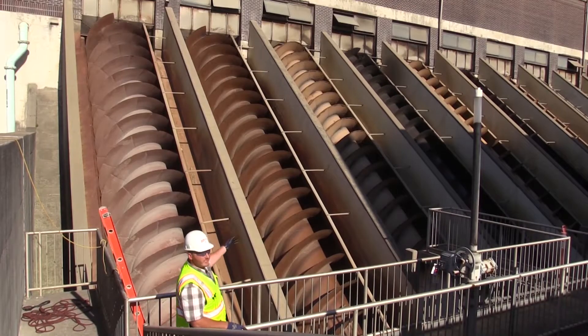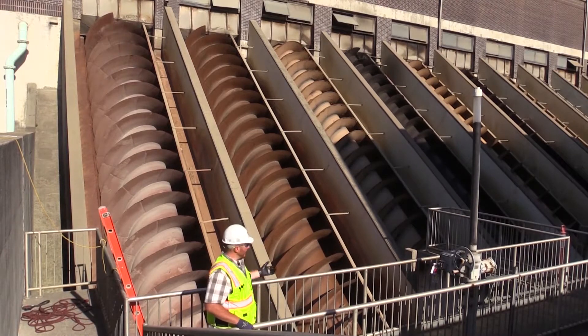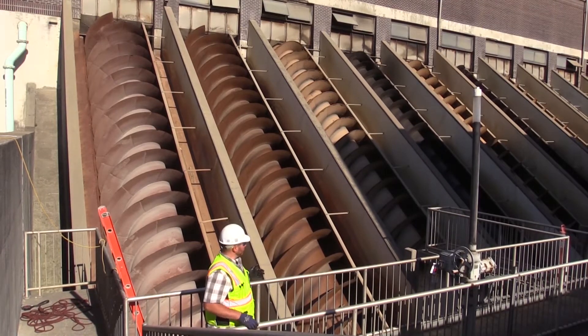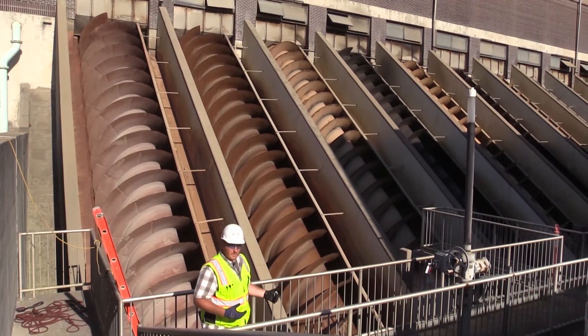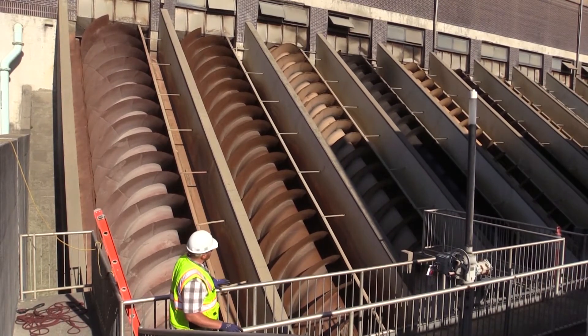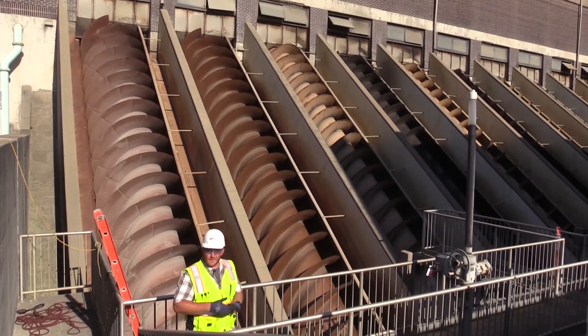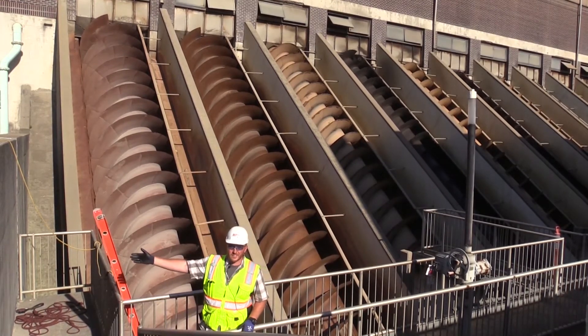Overall, there are 10 of these, so you could do 330 MGD on a daily basis. This is the raw sewage pump station. With these screws, the main goal here after the wastewater is screened is to get it to elevation so that it can gravity feed through the other parts of this facility.